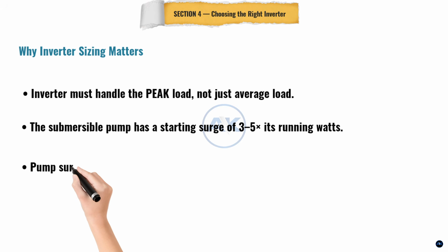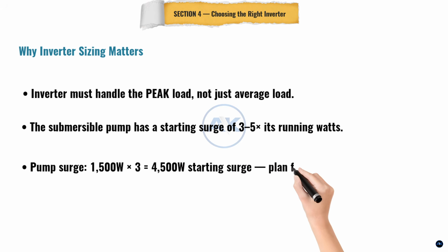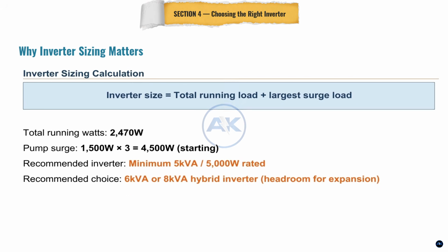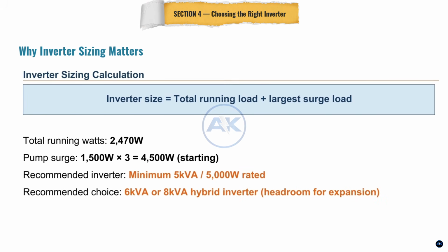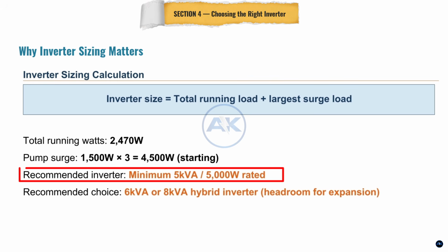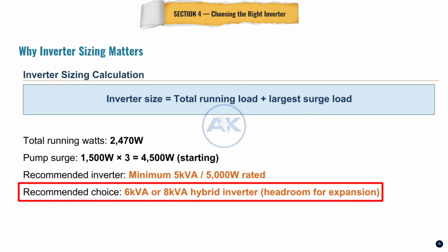The water pump is 1,500 running watts, but when it starts, the motor draws 3 to 5 times that, up to 4,500 watts of surge current for about 2 seconds. An undersized inverter will trip every time that pump starts, so we size for the surge, not just the running load. Total running load is 2,470 watts. Add the pump surge, we need a minimum 5 kilowatt inverter. I recommend going to 6 or 8 kilowatts. The extra headroom is worth it.